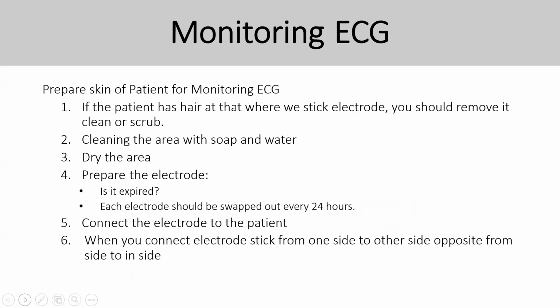So when you're doing ECG, basically one of the important parts is to prep the patient, basically to prepare the patient for ECG. This is one of the common problems that you're going to deal with users, because what happens is you're going to end up seeing expired electrodes, sometimes not enough ECG gel, sometimes the ECG electrode being used more than 24 hours. All this can cause not a good reading. Sometimes you're not going to get any reading, or the reading is not stable.